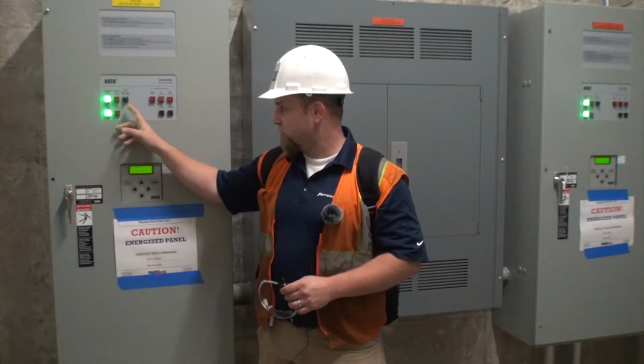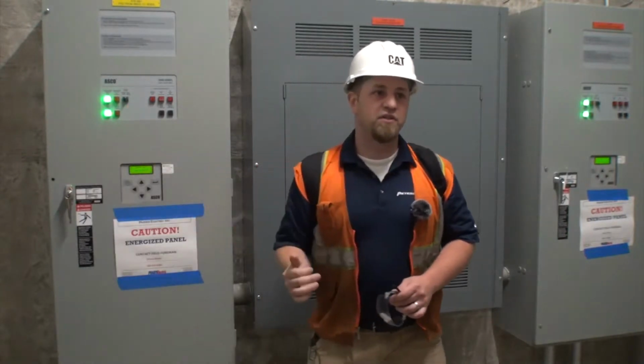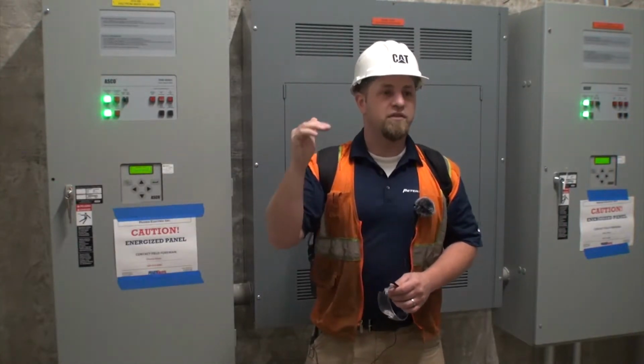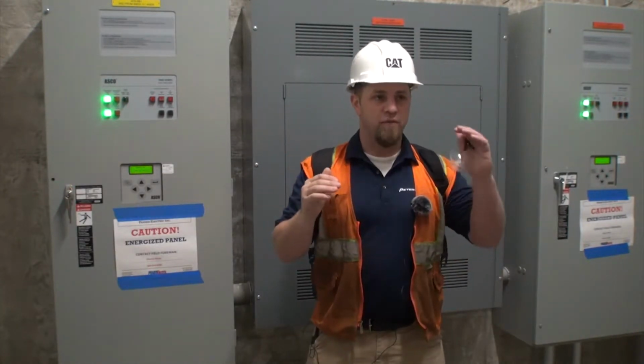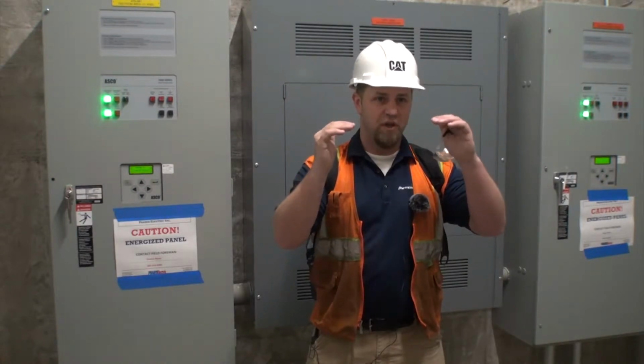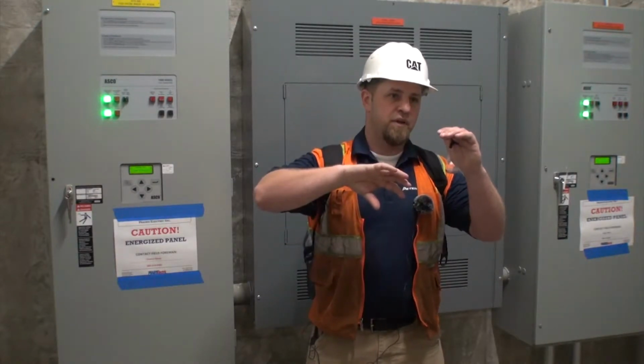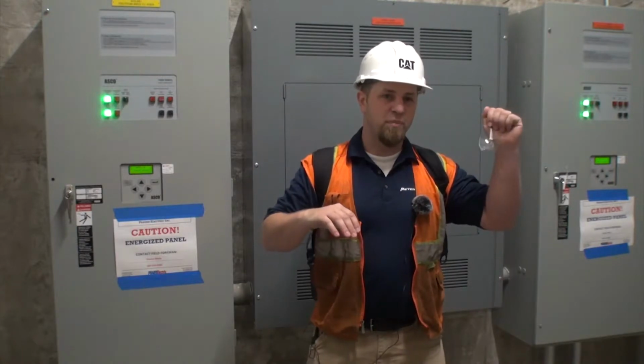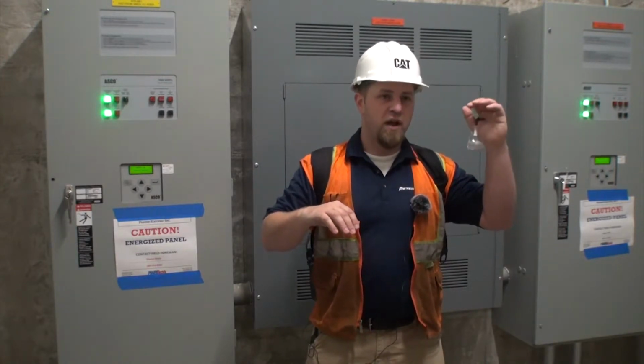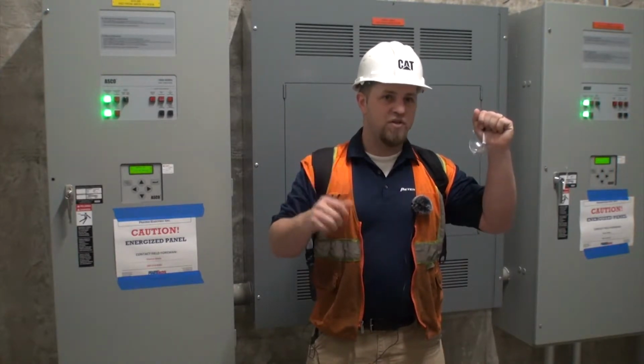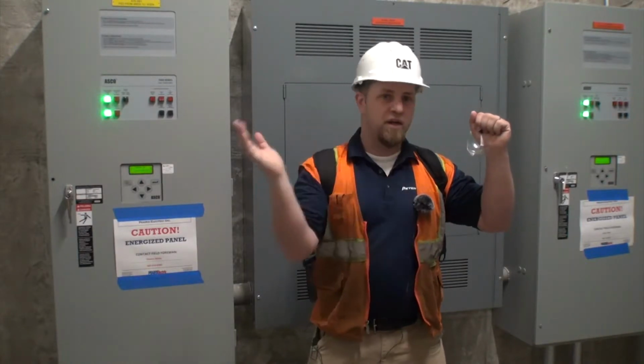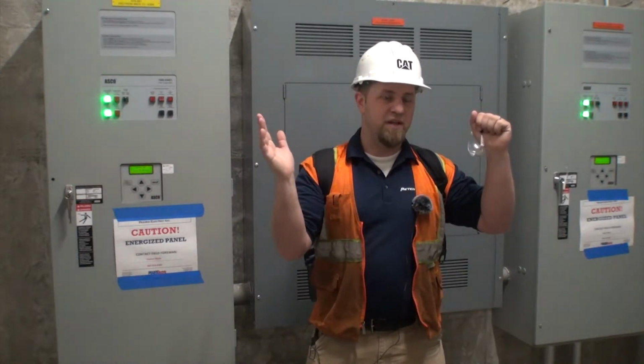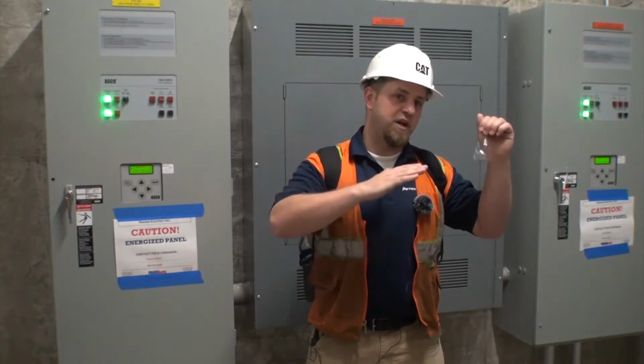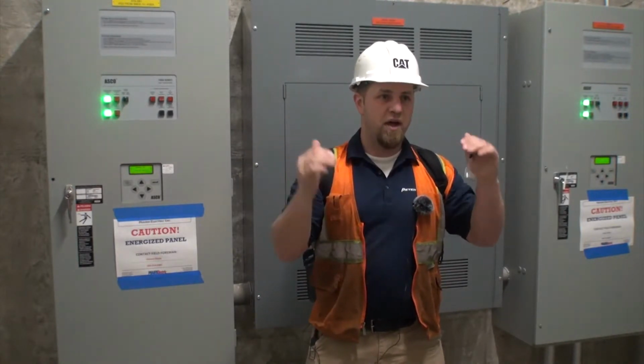The other benefit of doing it from here is you're actually going to start the generator, let it run, make sure voltage, hertz, and everything else is good, and then transfer — compared to closing your breaker, opening your breaker, losing power, then the generator has to start and transfer over. If there's something it doesn't like, it might never transfer back, so you always want to do it the other way.